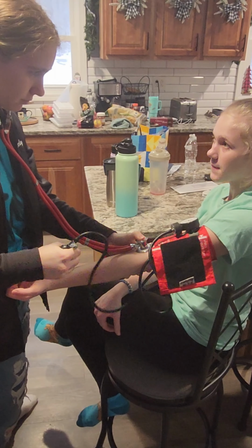Slowly turn the air release valve down while watching the pressure gauge. The pressure it's at when you first hear soft tapping sounds is the systolic pressure. Continue to reduce the pressure while listening closely to the brachial pulse and watching the pressure gauge. As you do this, the sound should become louder and more distinct. When the artery is no longer constricted and blood flows freely, these tapping sounds will disappear. The pressure at this point is the diastolic pressure.